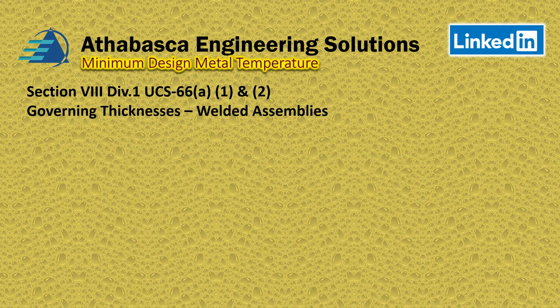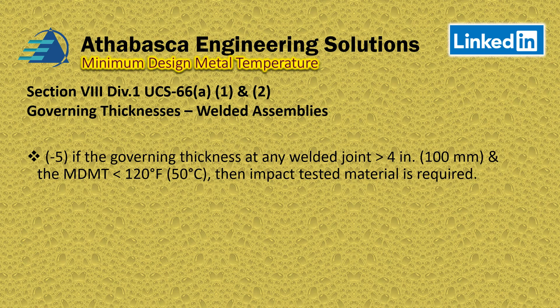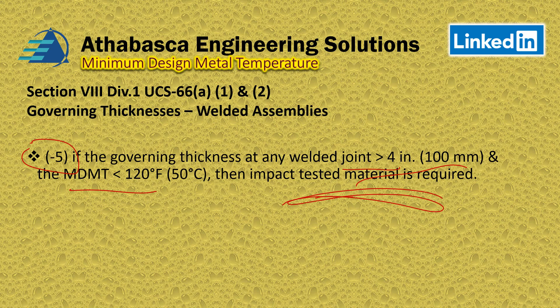A few more rules about welded assemblies: rule five says if the governing thickness of any welded joint is greater than four inches and less than 120°F, then impact testing is required for really thick joints. This has to do with the triaxial stresses found in very thick parts, which we touched on in an earlier video to understand why there are more restrictions for thicker parts.